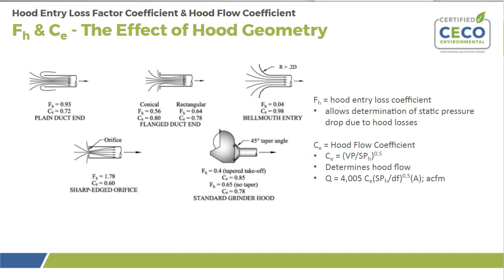I think it's worth mentioning that once we are able to determine these loss coefficients, along with the acceleration loss, we can figure out the static pressure of the hood. There's also the hood flow coefficient CE, and that then allows us to determine the overall flow rate at that hood. And at this point, I'm going to turn it over to Dale.